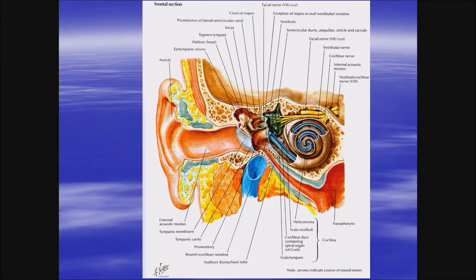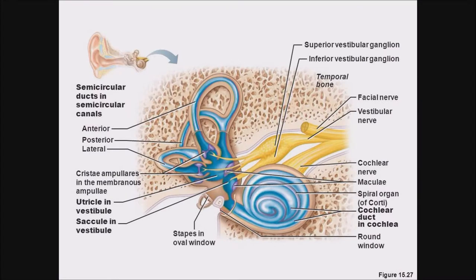Why can you use sound stimulation? Because the vestibular end organs are located behind the oval window, and normal sound does not stimulate the otolith organs. Using the right sound stimulation — 500 Hz at 90 decibels or clicks at 110 dB — the sound has enough power to cross and stimulate the otolith organs, sending an evoked potential down the vestibular nerve and through the vestibular pathway.